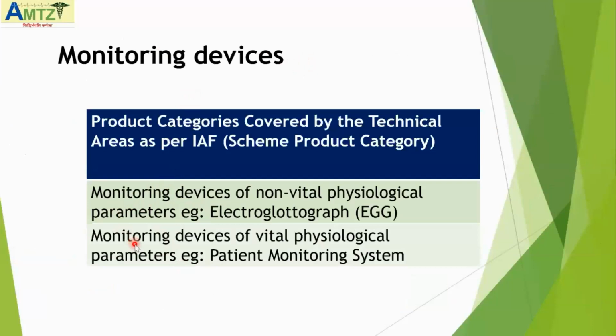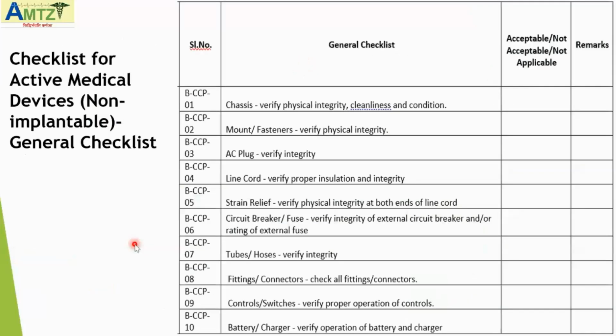Now let's see how the checklist looks. What we have put forward is the minimum. A particular hospital may include more points, which is always welcome, but at least this minimum checklist has to be maintained. Otherwise, the maintenance process won't be effective. Now I was talking about the second category, the active medical device, non-implantable. This is the general checklist, what you are seeing on the screen. For example, the first point in the checklist: chassis, verify the physical integrity, cleanliness, and condition.